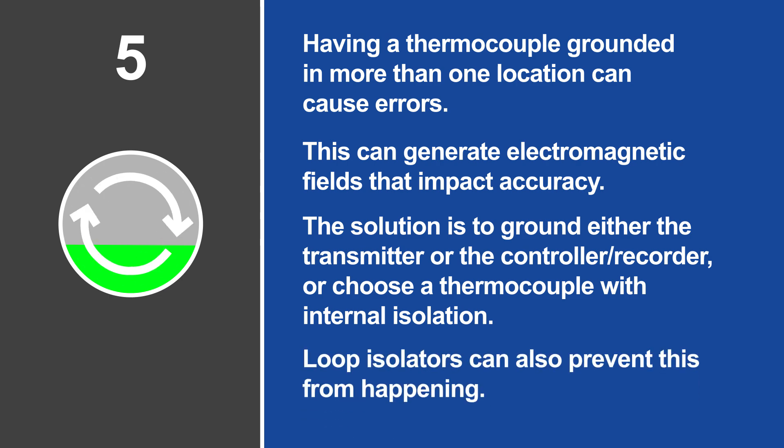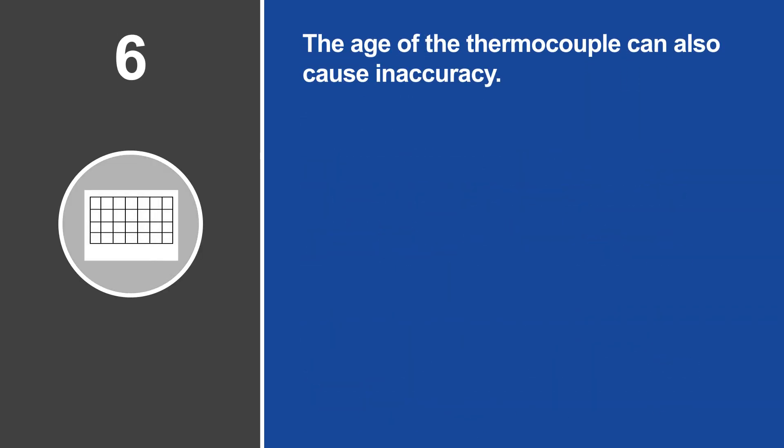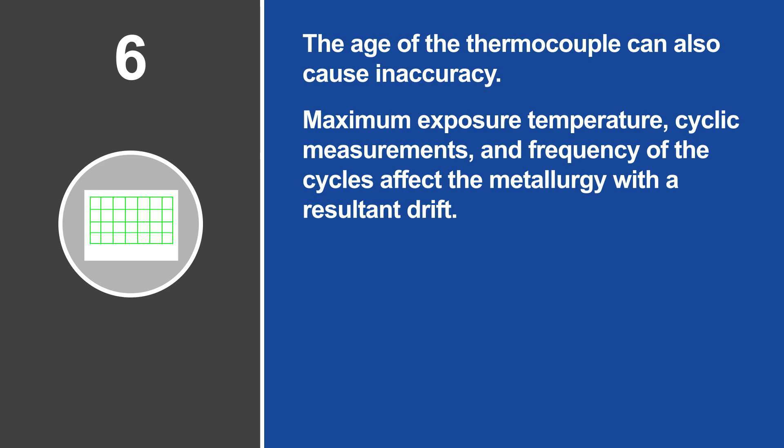The age of the thermocouple can also cause inaccuracy. Maximum exposure temperatures, cyclic measurements, and frequency of the cycles affect the metallurgy with a resultant drift, usually downward. If this happens, 10 to 20 degree Fahrenheit errors are common.